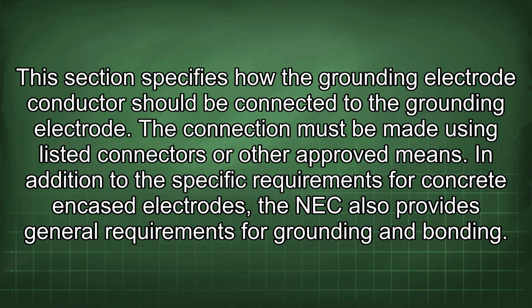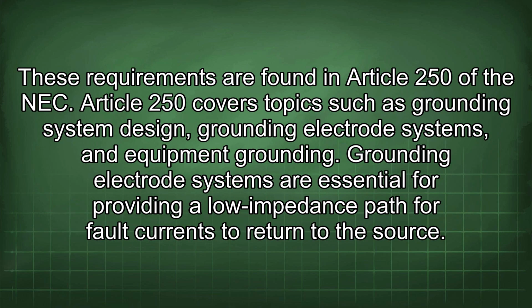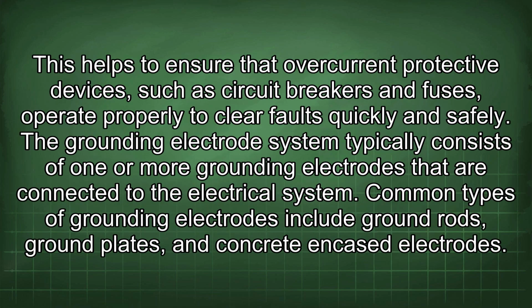In addition to the specific requirements for concrete encased electrodes, the NEC also provides general requirements for grounding and bonding. These requirements are found in Article 250 of the NEC. Article 250 covers topics such as grounding system design, grounding electrode systems, and equipment grounding. Grounding electrode systems are essential for providing a low-impedance path for fault currents to return to the source. This helps to ensure that overcurrent protective devices, such as circuit breakers and fuses, operate properly to clear faults quickly and safely.